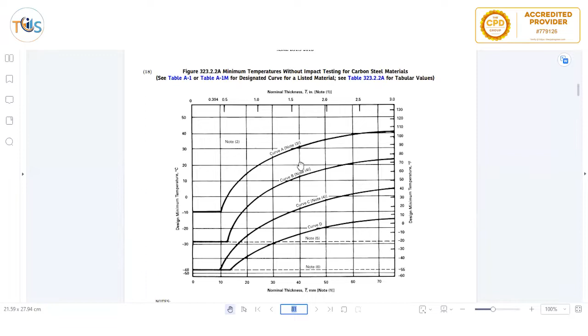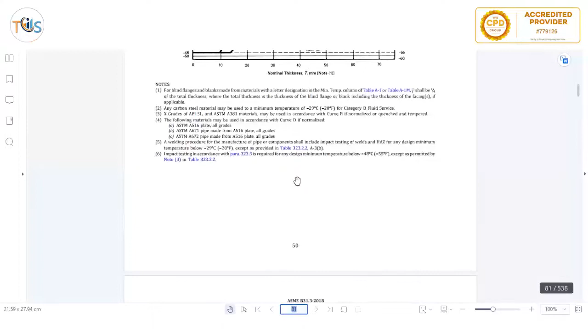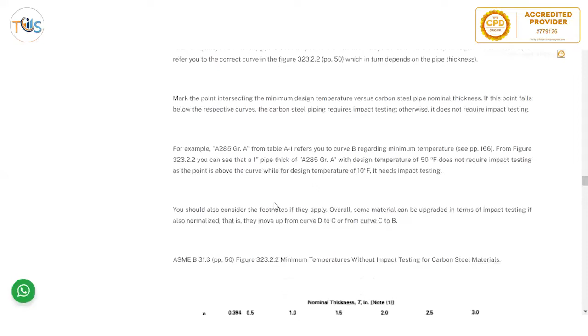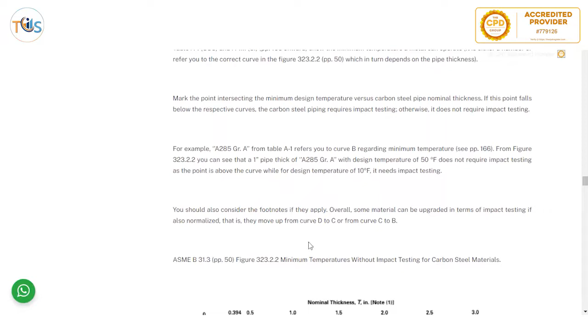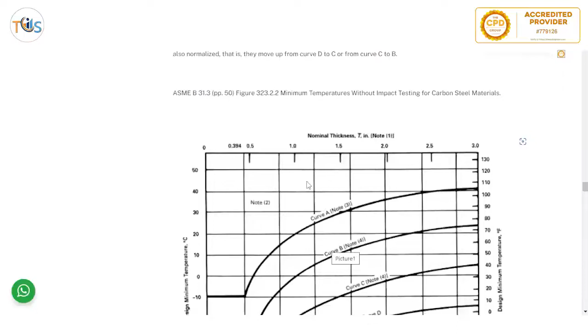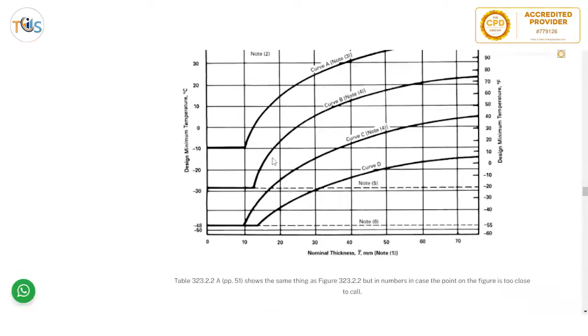So they will have 4 curves here. Now, if it's curve B, but the temperature is say 20, above the curve, where it intersects the thickness versus the working temperature, then no impact test is required. So it tells you whether impact test is required or not. We have explained here, we brought an example. Please go to this table and read our explanation here for this material and see how this works. We have also brought this here on page 50, which is in millimeter, and you can find the inch version on the subsequent graph.